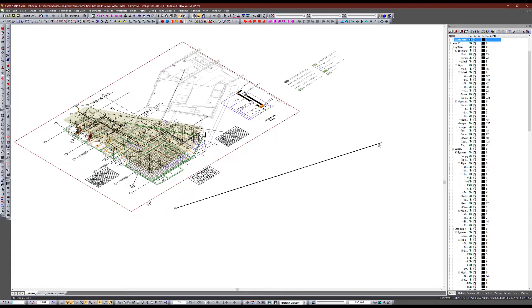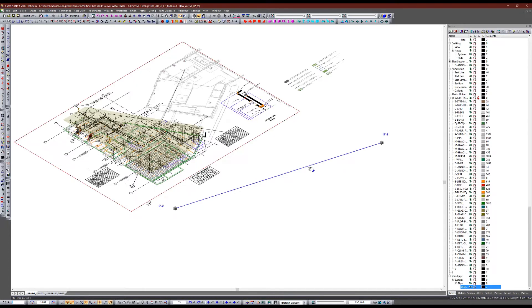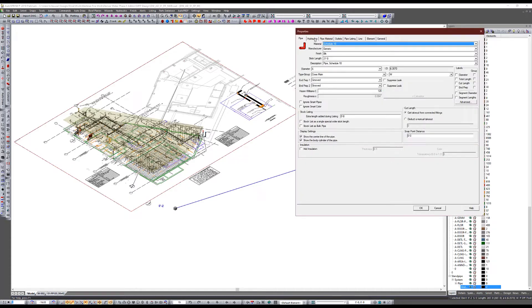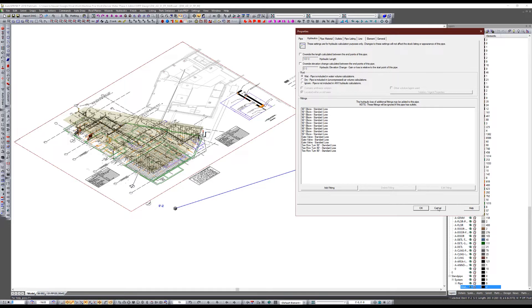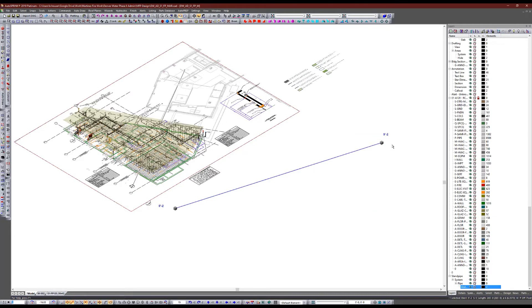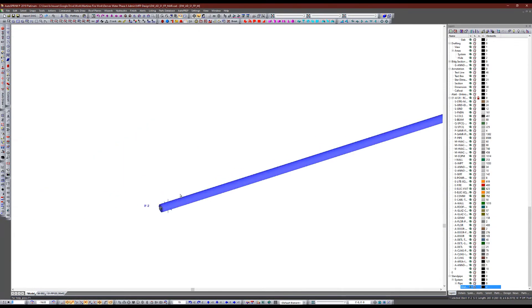The slope pipe feature was kind of intended more for dry systems and drainage slopes than for underground, but if you've got a nice even incremental length and you know what elevation you need to gain or lose over that total length, you could use it. But that's only if you want to show a physical elevation change. Otherwise, you could select the pipe, leave it flat, and simply specify an elevation gain in the override properties.